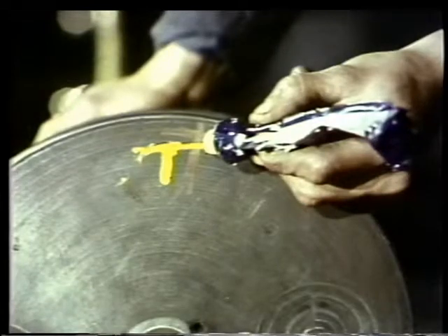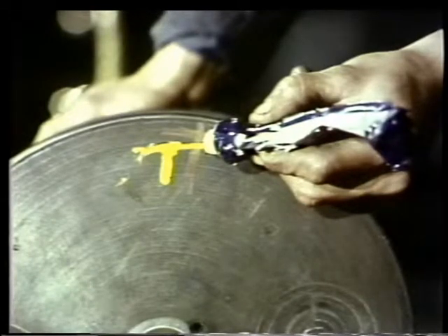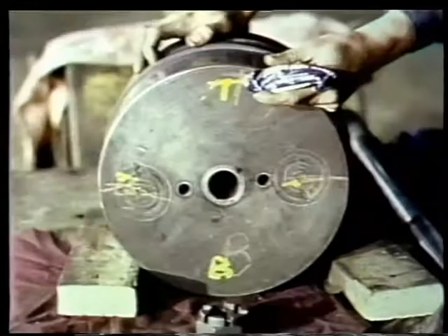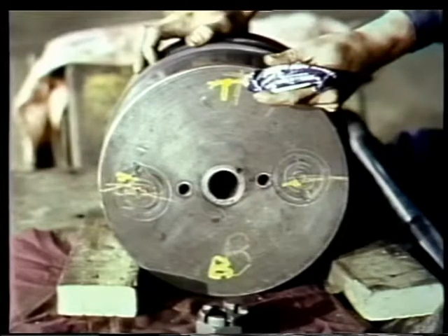Now, to avoid losing track of which side is which, we'll put a T for top on the worn side and a B for bottom on the opposite side. The last thing we'll do before beginning reassembly is grind the piston rod into the piston. Now, this is necessary whenever a piston rod's replaced to ensure a smooth, even fit. The fit must be perfect. A fit that is too loose initially will loosen even further during operation.